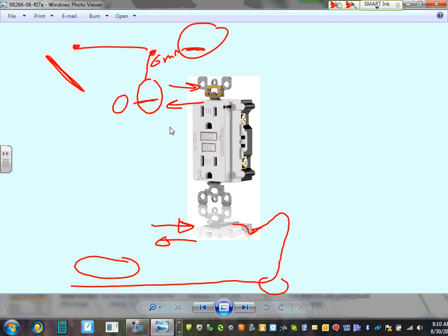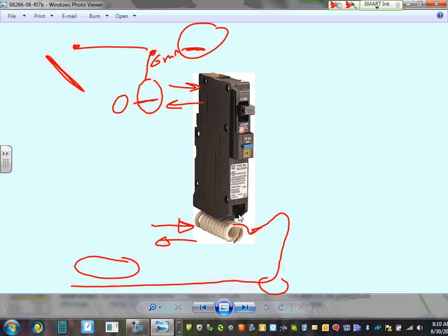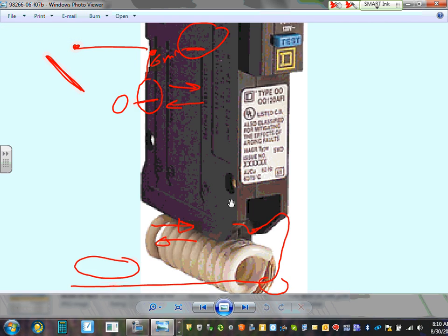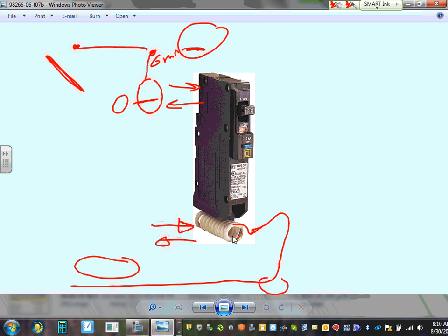You guys have seen it. There's a reset button. You're supposed to test these monthly. If you have a circuit breaker GFCI, which you're allowed to do, then you have... did you wire them, Adam, here with us? Yeah. So you have the neutral. You have to land a neutral independently. You can't share with anything else. You know that it comes with a neutral device. So you take your hot, and then a hot and a neutral come into that device. So that has to go land into your neutral bar. So you got your in and out for this circuit, and so the neutral.